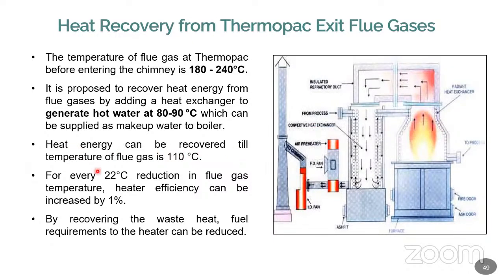Heat energy can be recovered till the temperature of the flue gas is 110. Even if it is 110, you can recover heat from the flue gas. Normally, a 22 degree temperature reduction in the flue gas will save 1% of the fuel in the system. So waste heat recovery in the thermal system is going to be very adaptive. Most of the time, it is economical also.